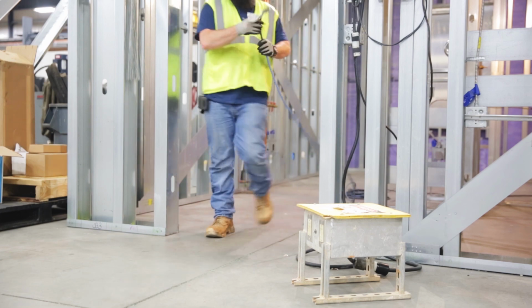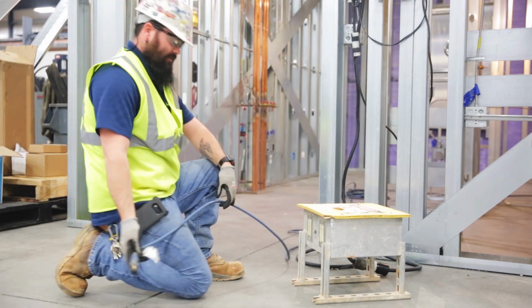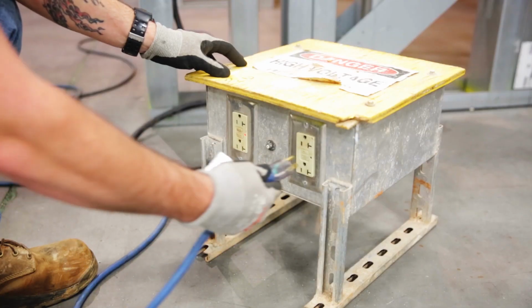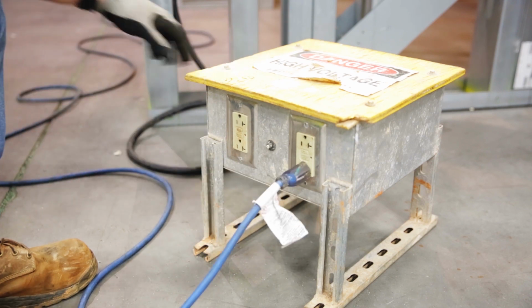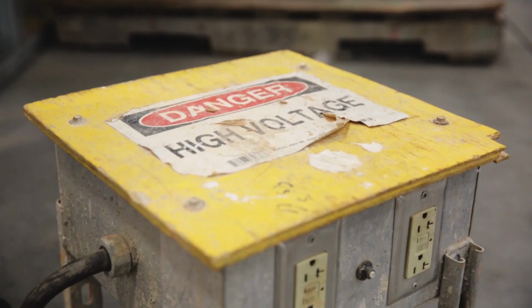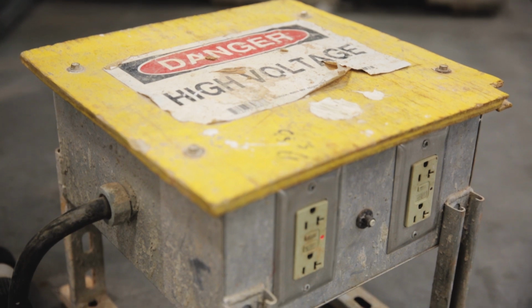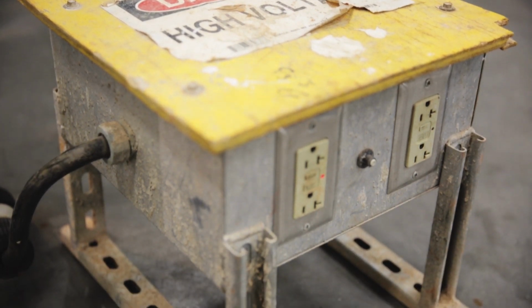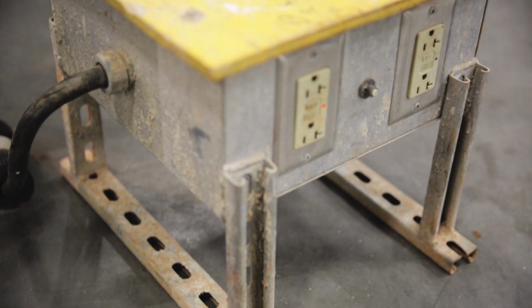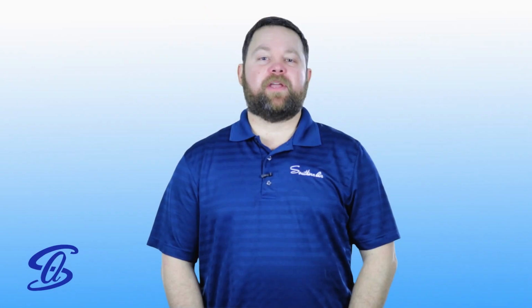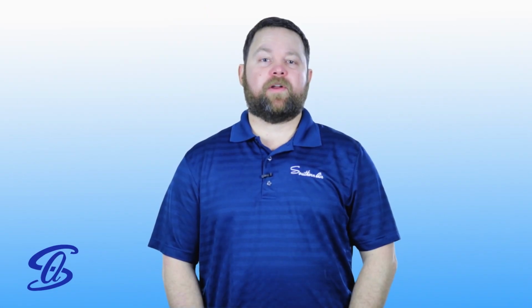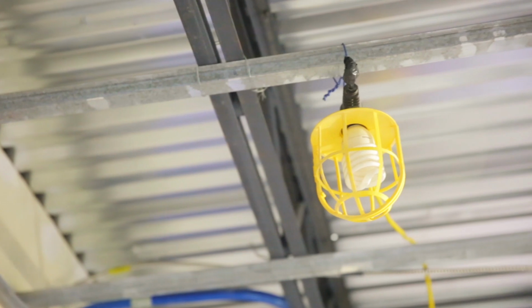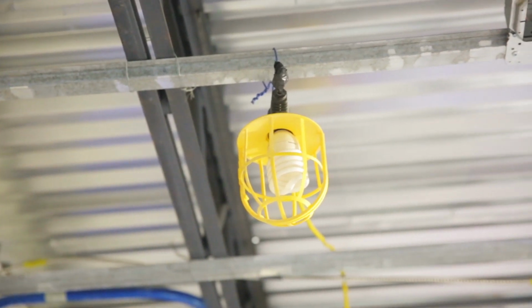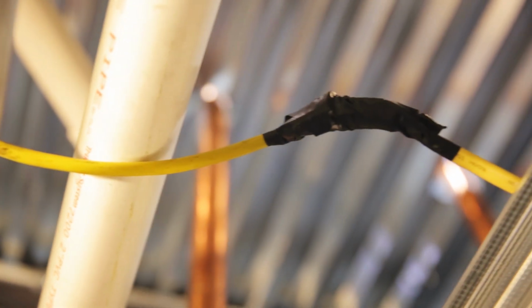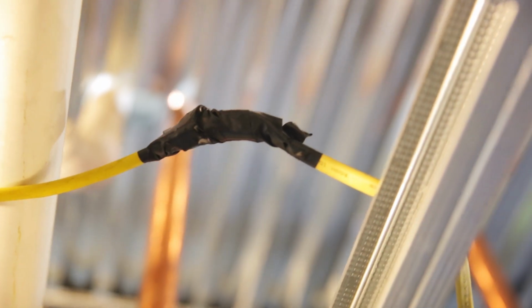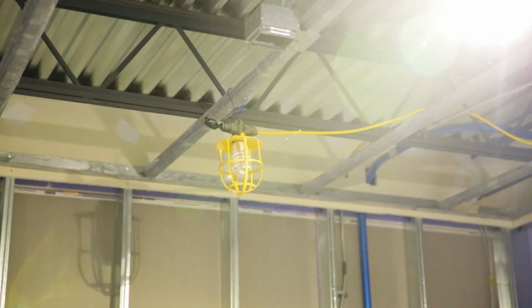Spider boxes plug directly into temporary power panels and are placed strategically throughout job sites to give 120-volt electrical access to all subcontractors. This allows a safe method for contractors to utilize their electrical tools, which plug directly into these boxes. Temporary lighting will either be 120-volt stringer lighting or 24-volt LED lighting. 120-volt lighting should always be hung in a non-conductive manner with splices that are wire nutted, electric taped, and no lower than 8 feet from the floor.